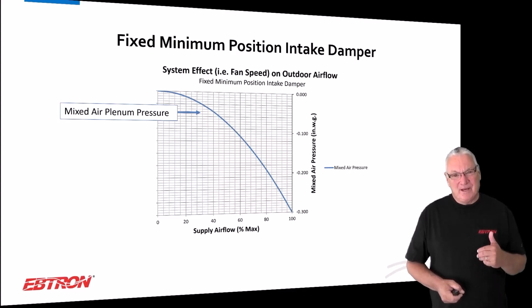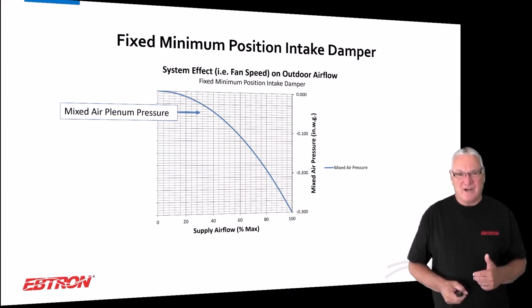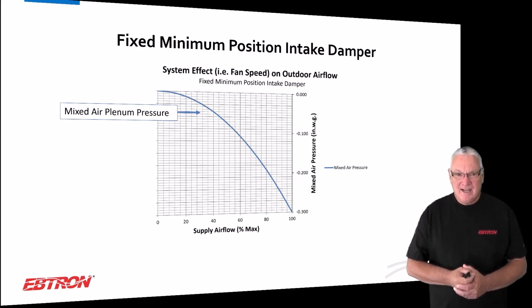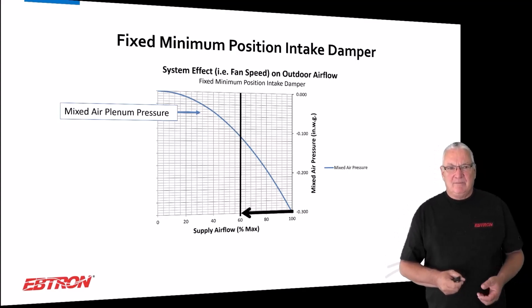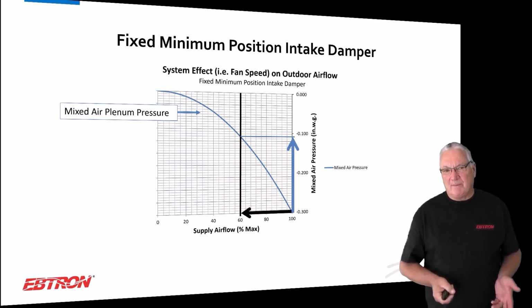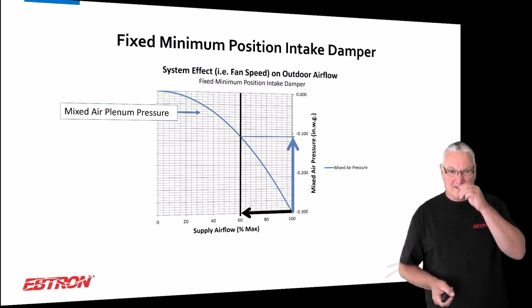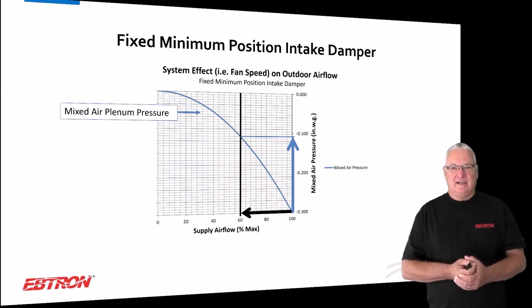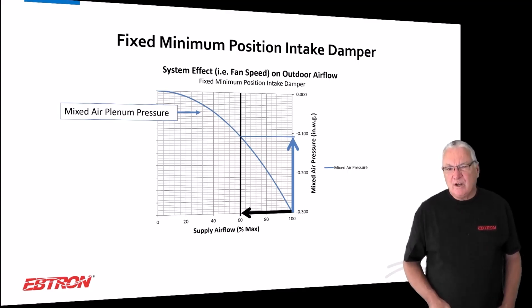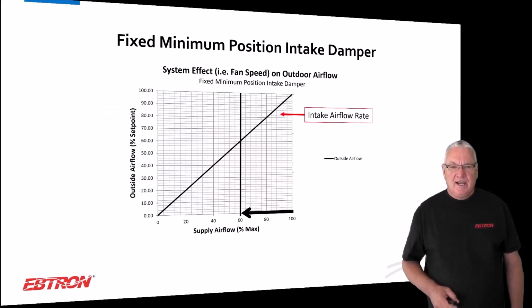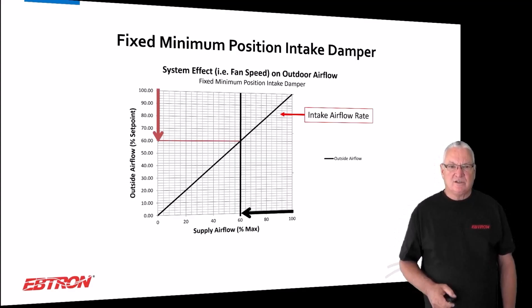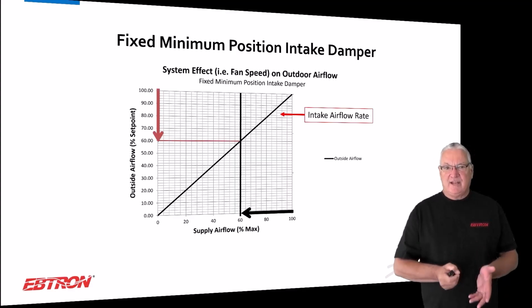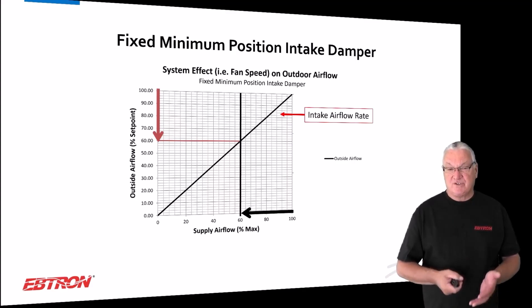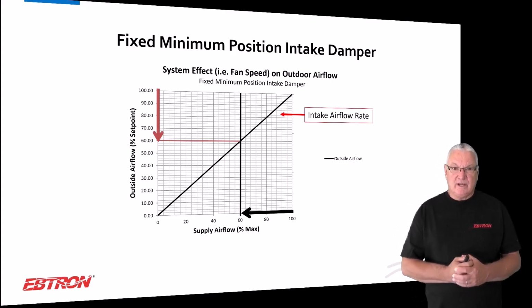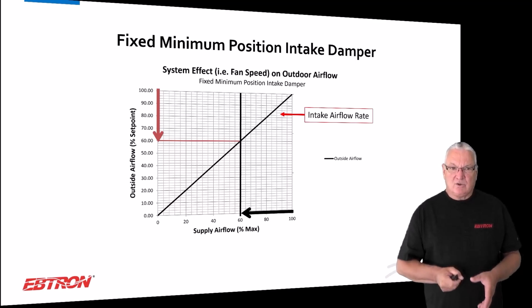But if you looked at the mixing box plenum pressure in this system, it would follow this basic square root relationship, okay? As the supply air flow drops, the mixing box plenum pressure would drop. And I'm going to just go from 100% supply to 60% supply there on that horizontal axis. And in this particular example, we'd almost have a 0.2 of an inch change in pressure. And that 0.2 of an inch change in pressure would have resulted in a linear reduction of the airflow rate. That's what happens on these systems, especially this simple recirculating air handler. So we go from 100% to 60% supply. The outdoor airflow went from whatever you set it to 60%, okay?